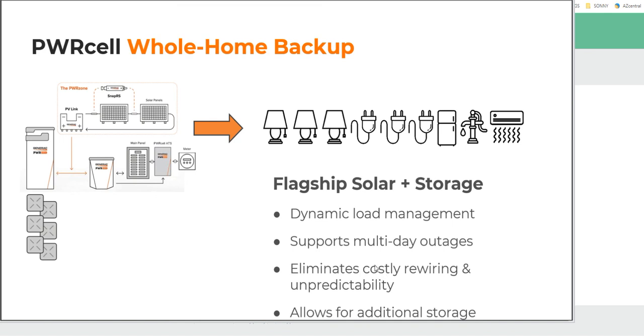Rather than breaking out a protected loads panel, we install smart management modules in line between the load and the service panel. These SMMs look for a frequency signal from the inverter — they don't need comm lines or Cat5 cables, they communicate over the power lines. So if you need to install one at the pool pump instead of the service panel, no problem. Anywhere in line between the breaker and the load is all the SMMs care about, giving lots of flexibility in managing loads for a good backup experience.